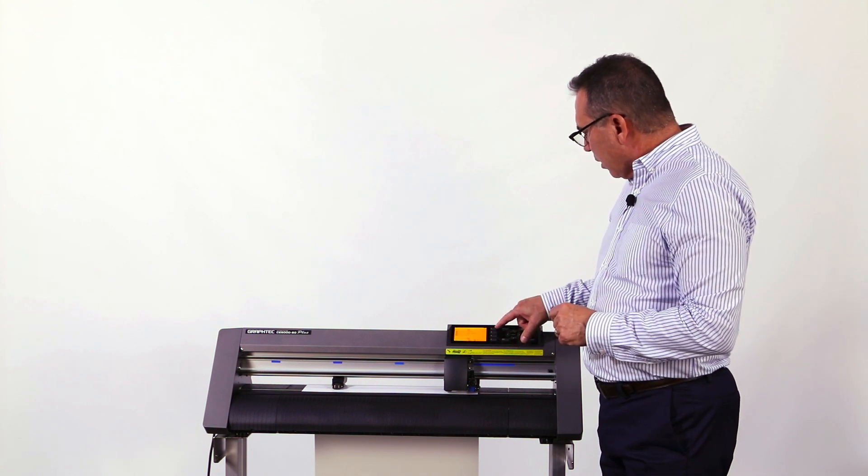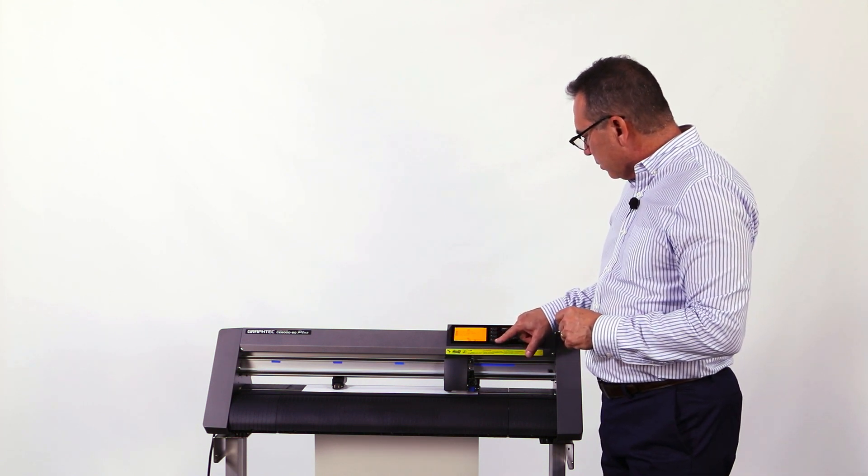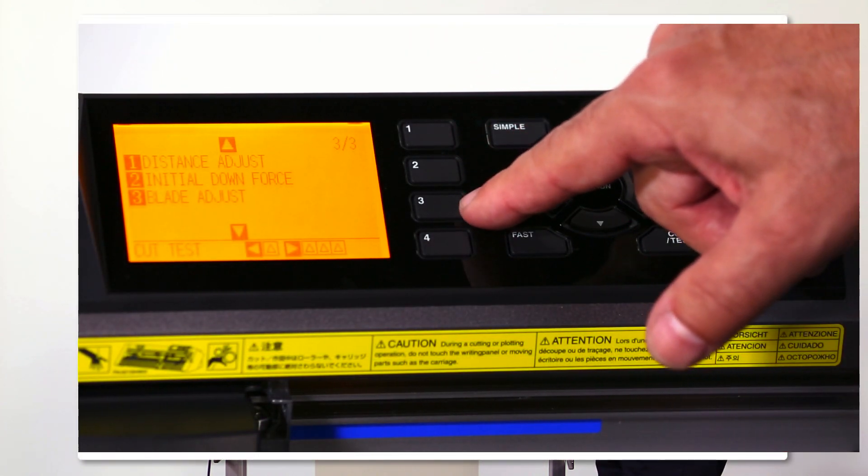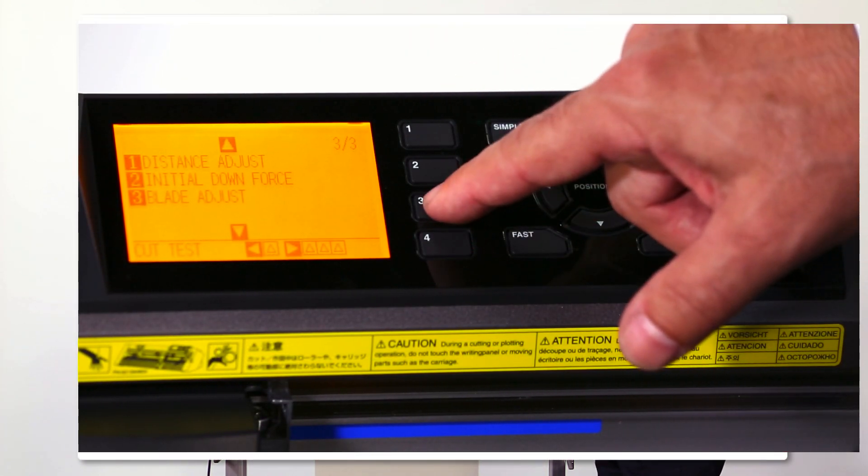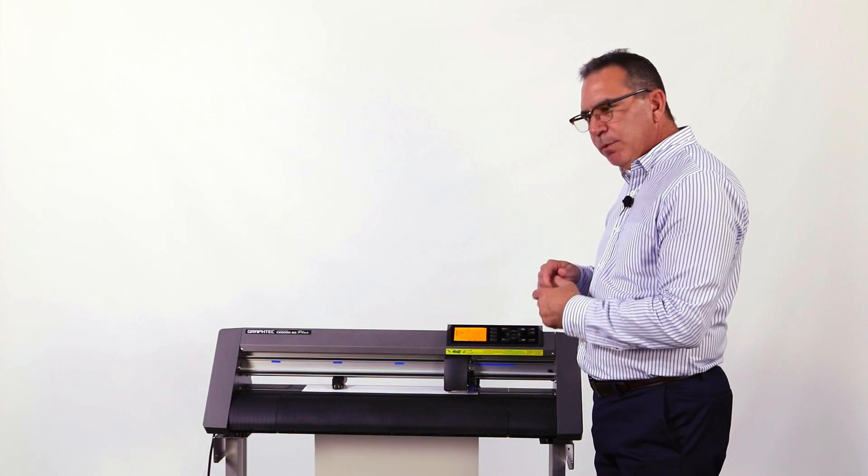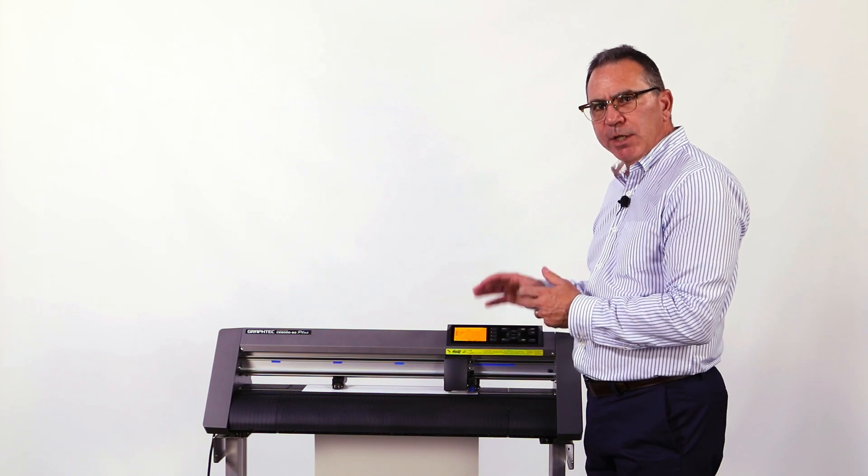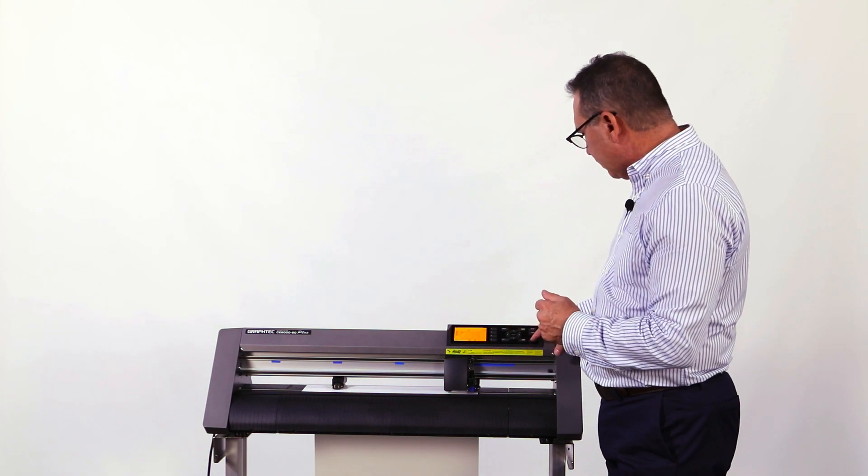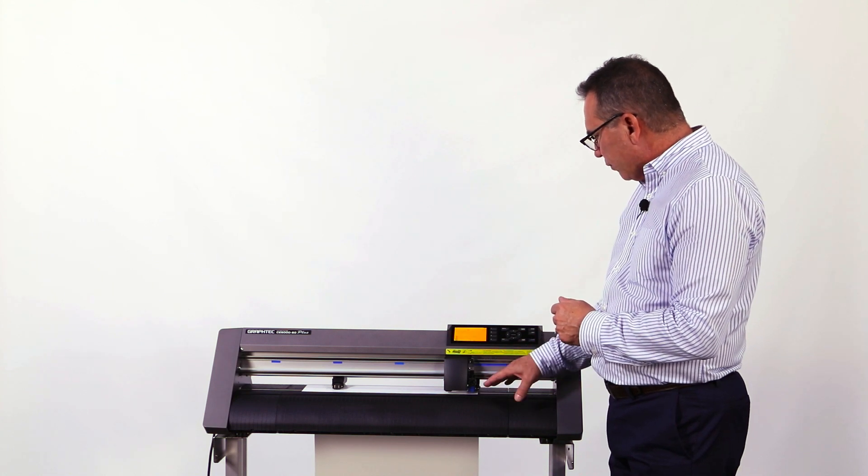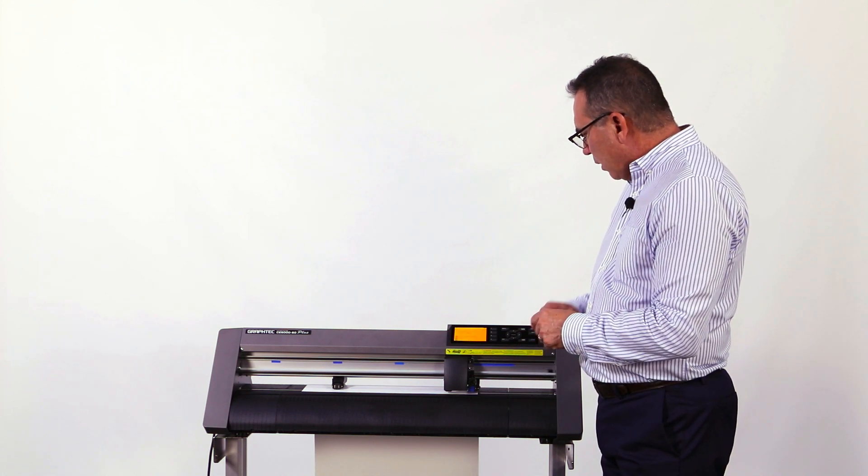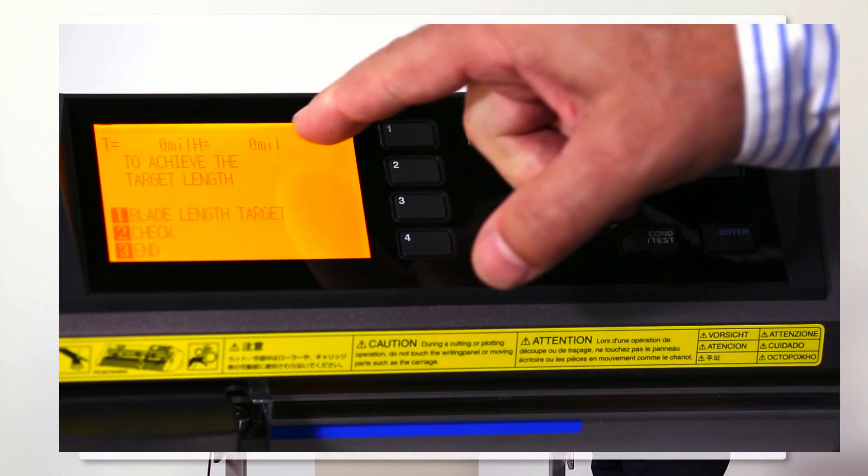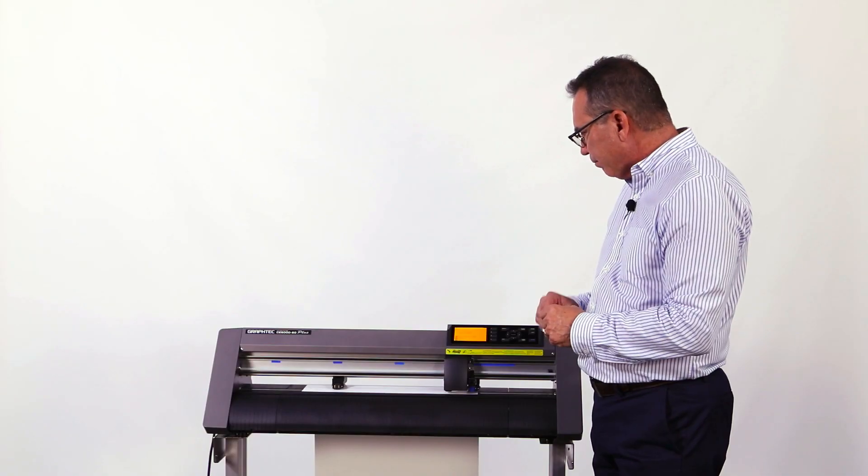There's a column of buttons located in the middle of the control panel labeled one, two, three, four. So I'm going to hit three for blade adjust. It's going to tell me to turn the tip counterclockwise to retract the blade. We've already done that, so I'm going to just hit enter. The tool holder is going to go up and down and set the zero position. Now the front panel reads zero mils.